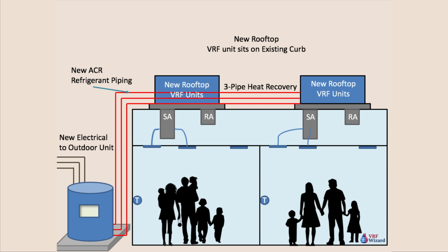The other good thing is now your branch selector or distribution box, your multi-port distribution box, is located within that outdoor package VRF unit. You don't have to hang it in the attic and run additional piping. It's all piped. So now the downstream side of that distribution box is already pre-piped to the indoor coil. That's all piped within the packaged VRF housing. Before, you would have to do that downstream piping as additional work. These units will handle medium static pressure.